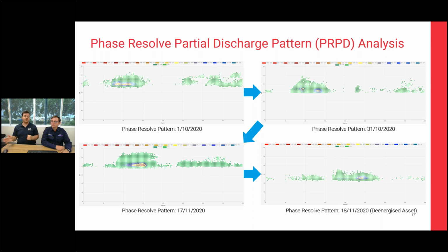That's what we worked quite closely with Brody and the team on as we trended these over time, and we ended up getting some great results. So from the partial discharge point of view, that's how we accomplished it, and how we all worked together. We had a lot of alarms set so if things were trending up, we'd know immediately. But in the end, the calls we made and the information passed on to Powerlink for their decisions was primarily based on the phase plot analysis.